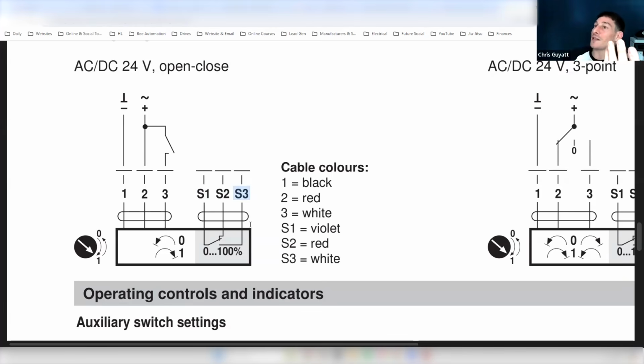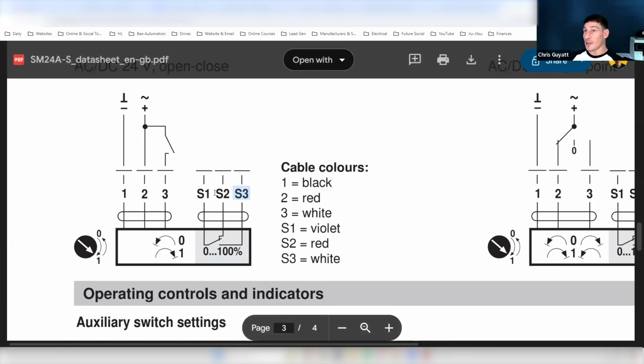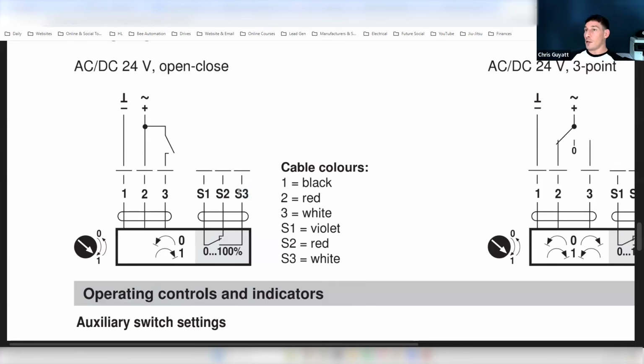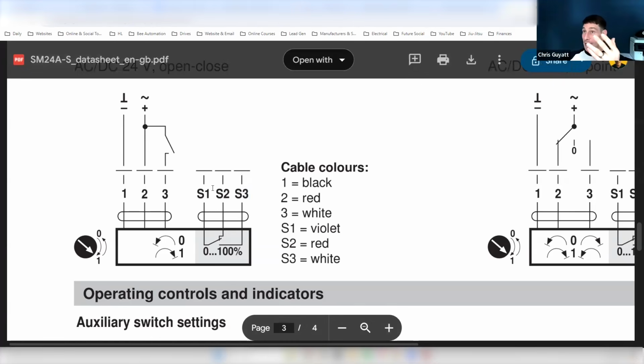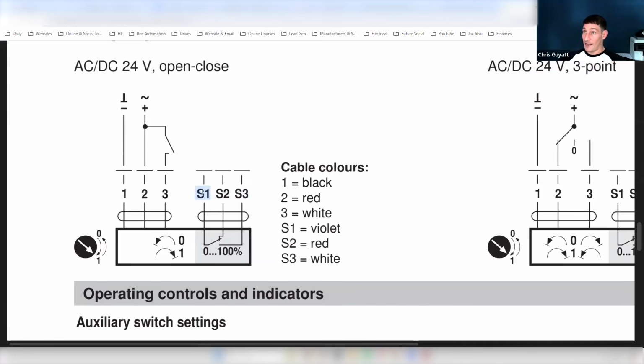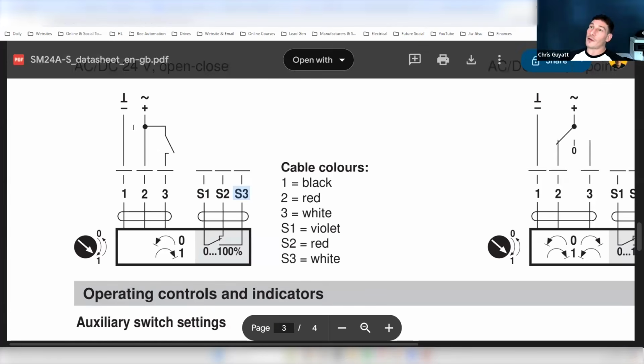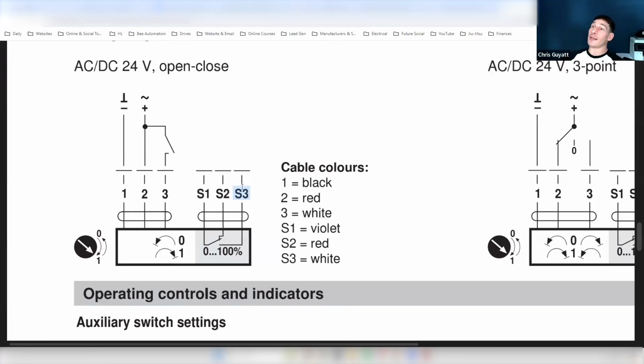Yeah. Which then, going a step further, you might want to use these for external monitoring. So we can log into the system remotely as BMS engineers, and whoever the engineer on site is, maybe a heating engineer or ventilation engineer, we can see the state of this vent remotely just from having these two, S1 and S3, wired into our BMS and then into our PLC. And we can then control this remotely and see that these statuses are changing.